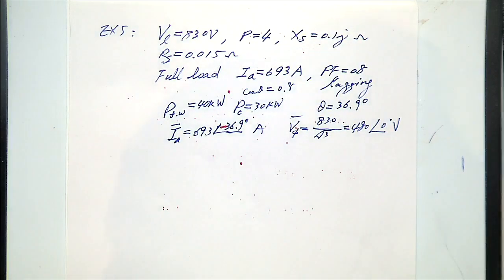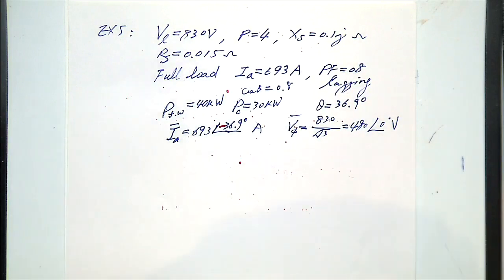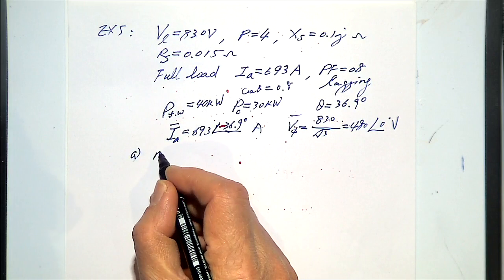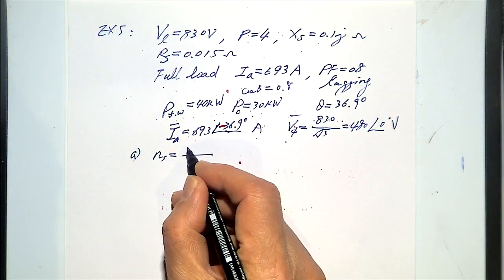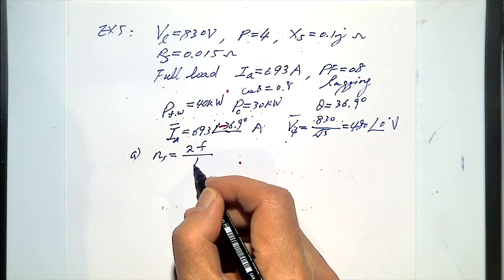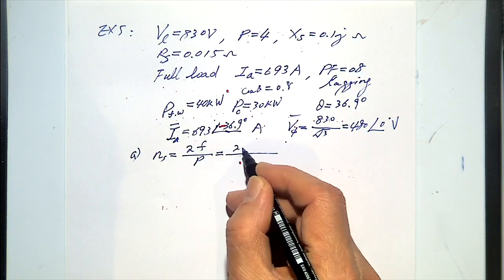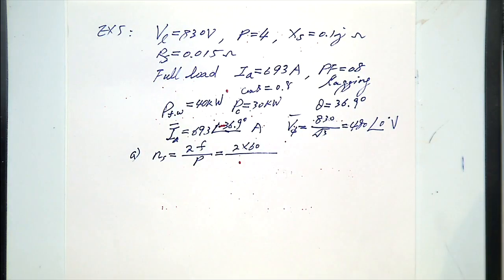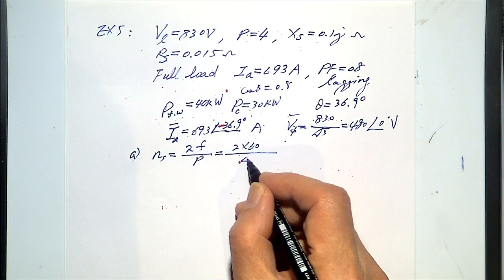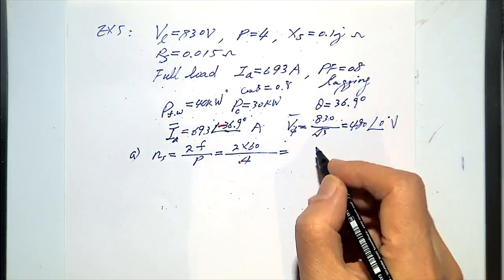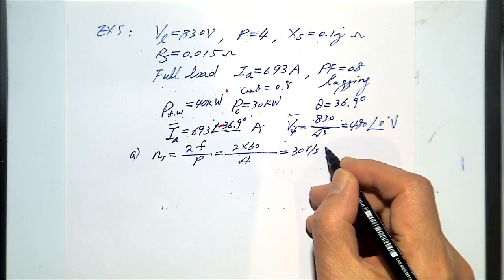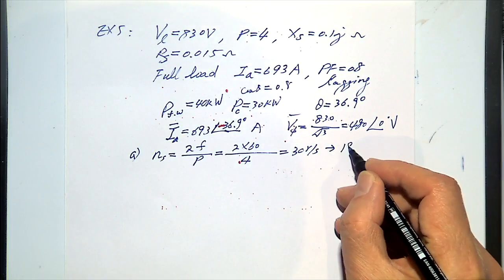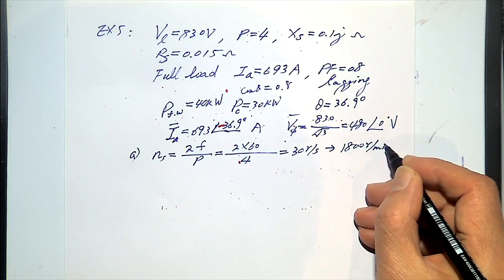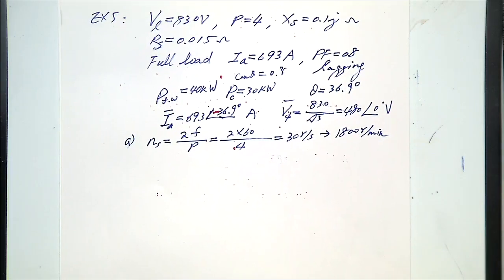Then the first question asks, what's the rotating speed? Everybody must be able to do this. The rotating speed is 2F divided by P: 2 times 60 is the frequency, divided by P equals 4. This gives rotations per second, which is 30 rotations per second, or 1,800 rotations per minute.